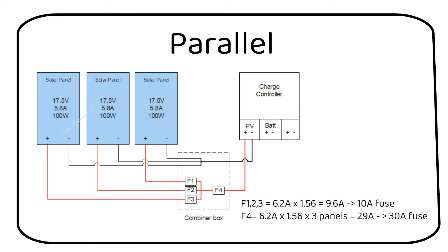We now need to calculate the fuse size for F4. We need to use the short circuit current and multiply it by 3 panels. Then we multiply it by the safety factor of 1.56 and we get 29A. We will use a 30A fuse for F4.